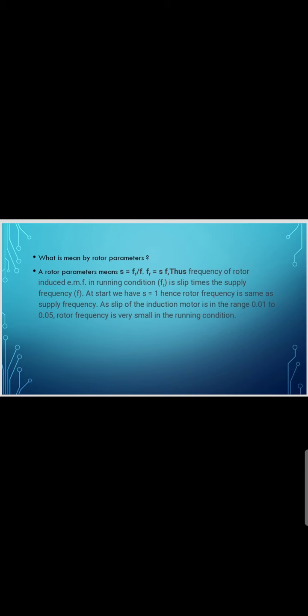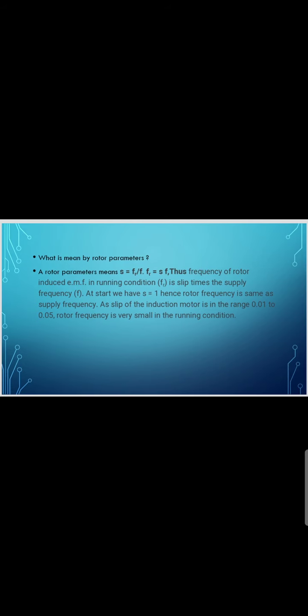Thus the frequency of rotor induced EMF in running condition, Fr, is slip times the supply frequency. At start we have S equal to 1, hence rotor frequency is the same as supply frequency. The slip of the induction motor is in the range 0.01 to 0.05. Rotor frequency is very small in the running condition.